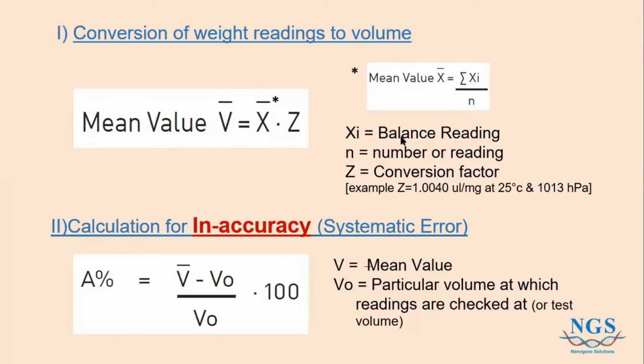So what is really the difference between inaccuracy and imprecision? Inaccuracy is also known as systematic error. It's kind of like an error that you can predict. It's always going to be a bit higher or maybe a bit lower, and it may be caused by your pipette. So if you have trouble staying within the range of inaccuracy, it can mean that your pipette needs some more calibration.